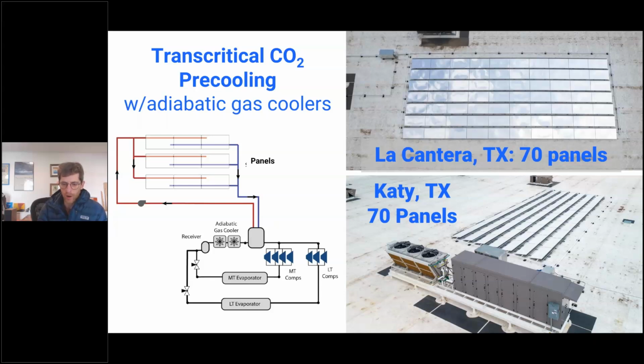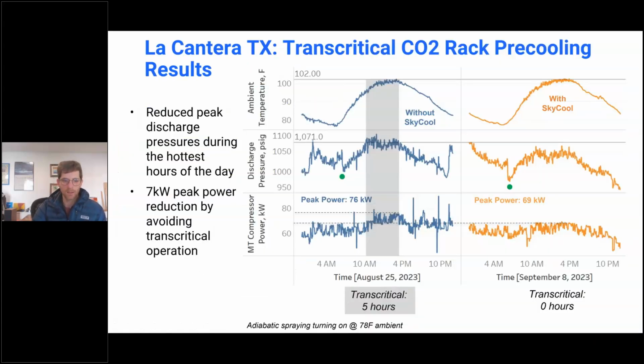It sprays water in the summer when it's particularly hot outside as a way to lower the discharge pressure when it's transcritical. Adding the panels allowed the discharge pressure to come down even more, and it allowed the entire system to not be transcritical during certain ambient conditions.